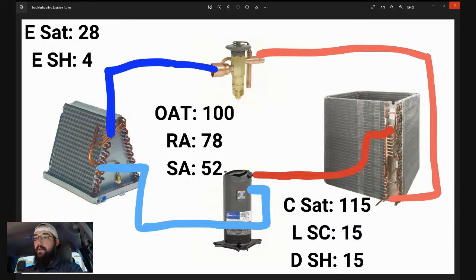So what are we thinking? What do you check next? Filter? We want to go filter on it. So you check the filter. It's got a 1-inch pleated. It's not dirty, but it's not clean. So pull the filter out. Readings aren't affected. Very, very marginal, not enough to document.